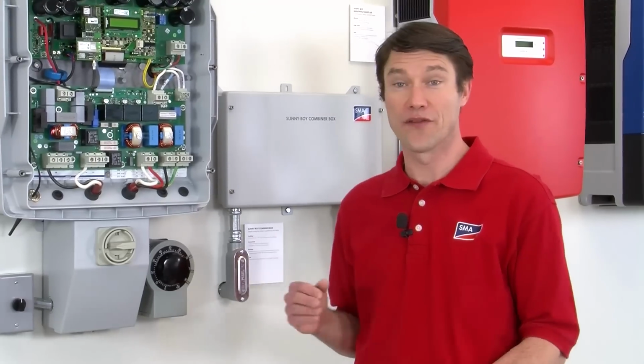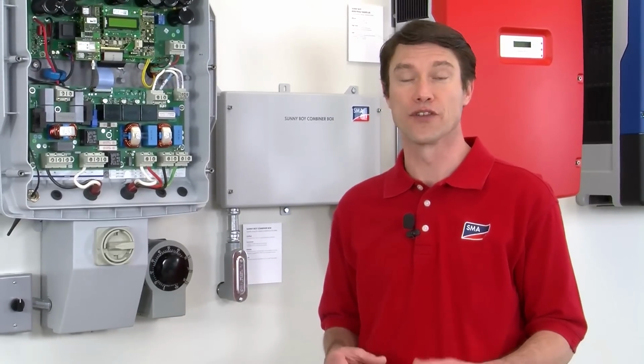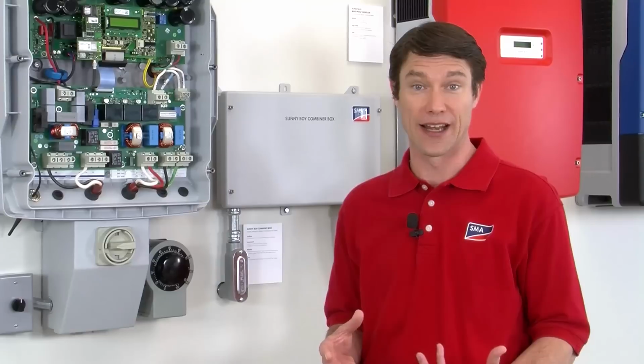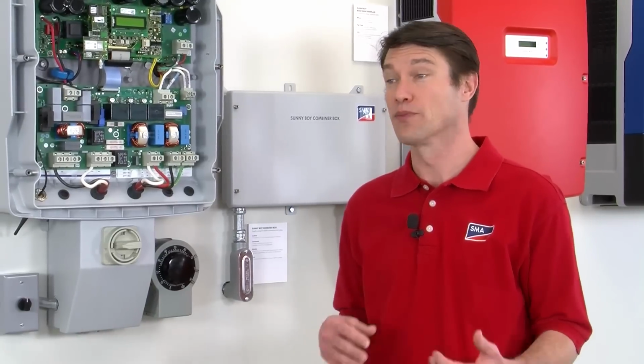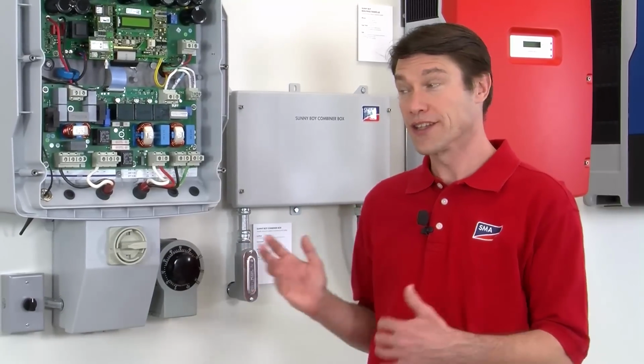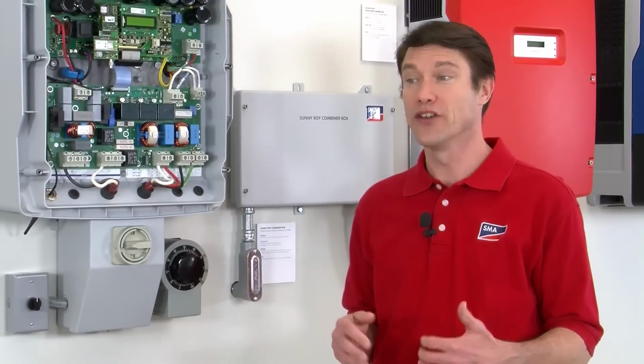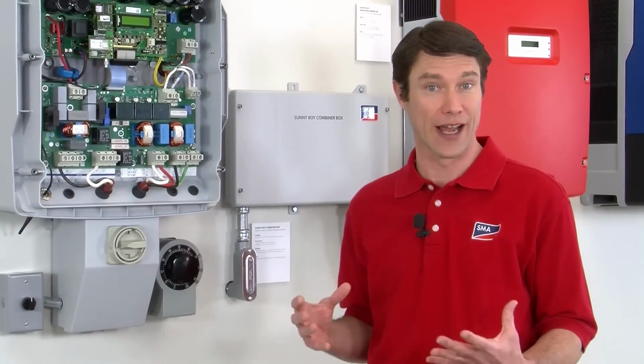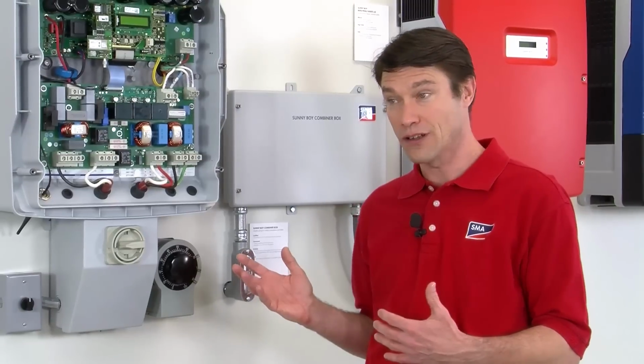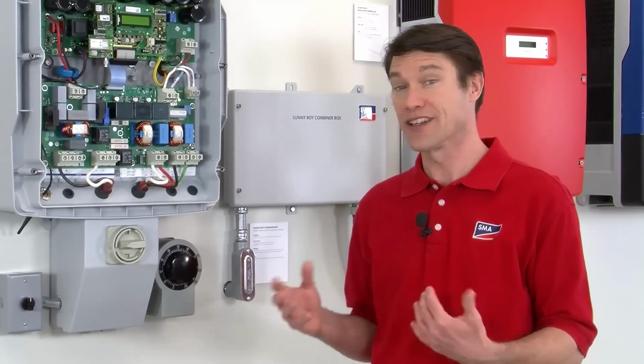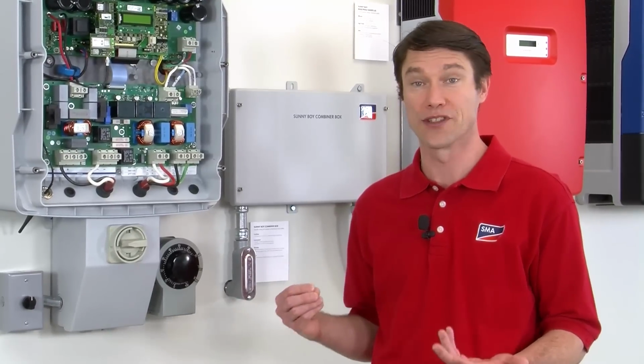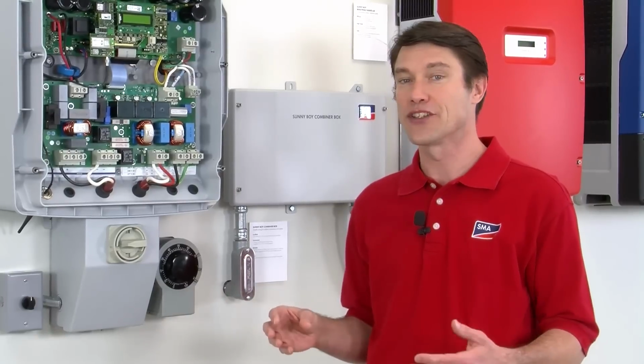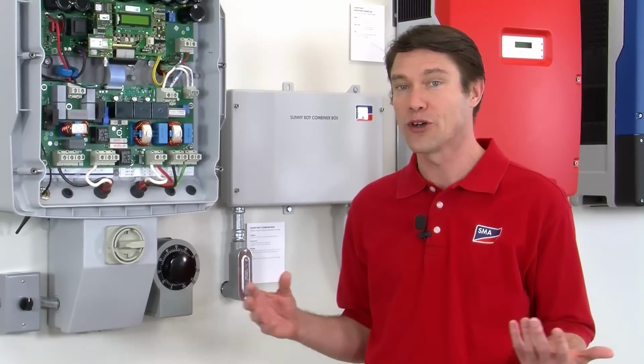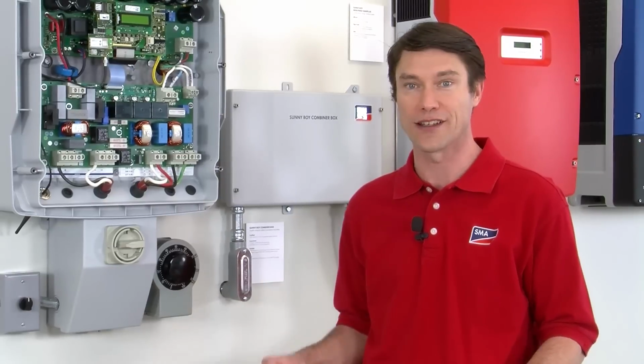with a VAC error. Now, this particular cause of a VAC error highlights the importance of doing proper system design and calculating voltage drops before installation. Because at this point, if that's really the culprit, you need to replace the wire with a wire of bigger diameter. And depending on the install, that can be an involved task. It might be very simple as pulling a larger wire through a small piece of conduit, but if it's trenching across under a road or across an object, then that becomes really costly.